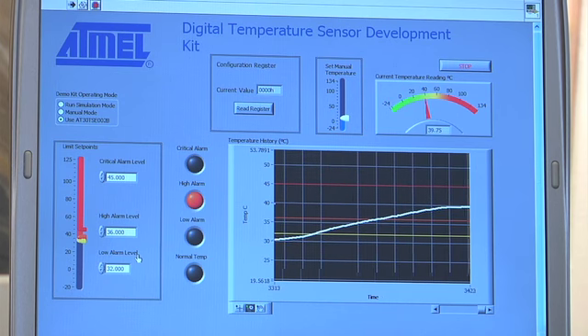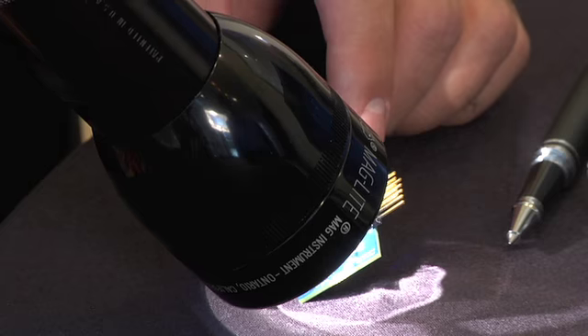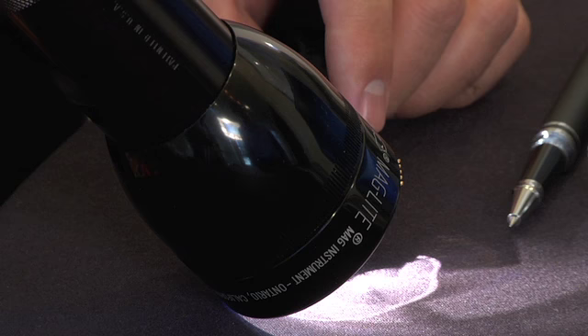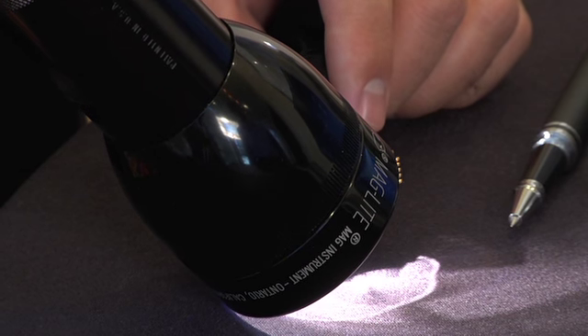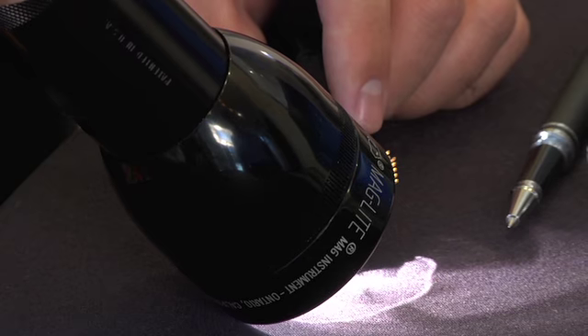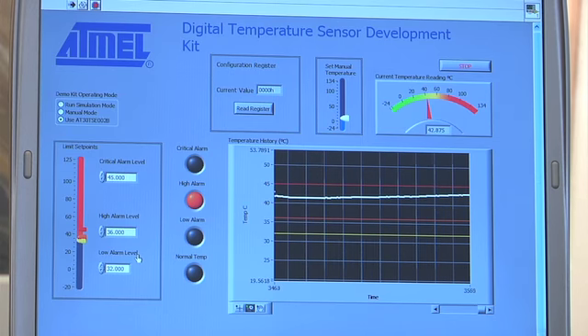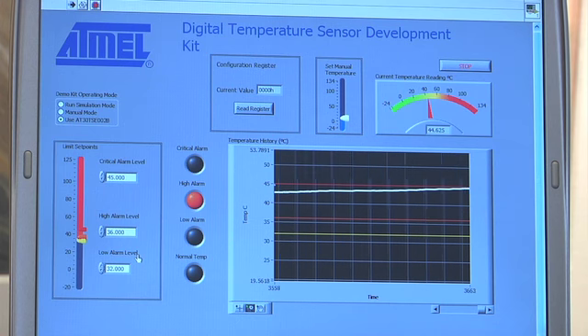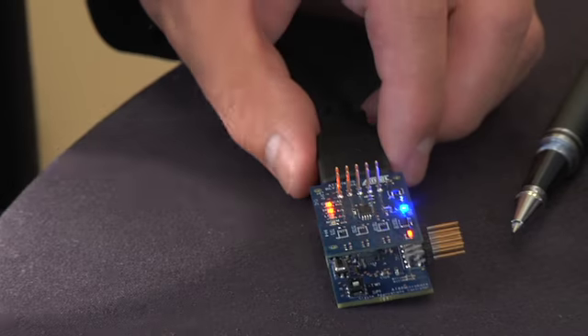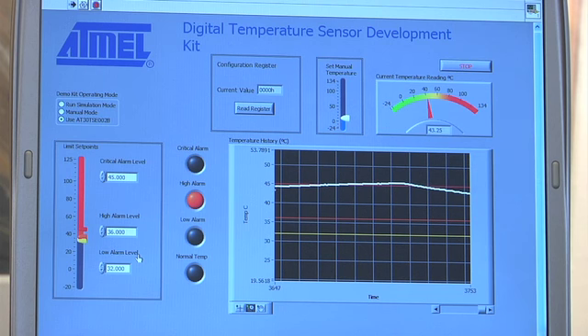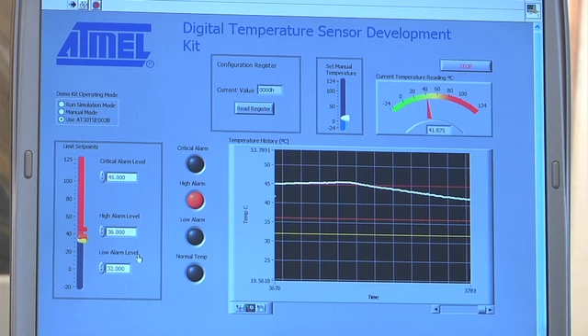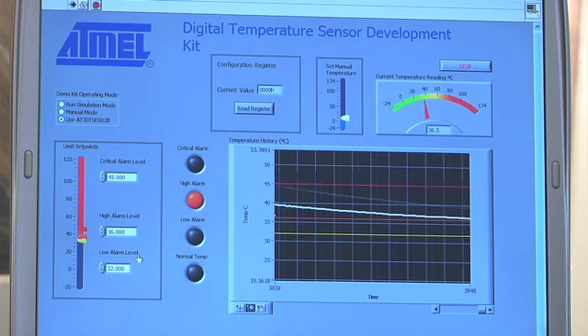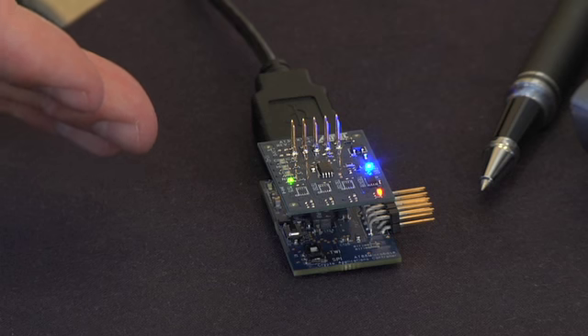And you can see the high alarm limit's already been exceeded. And if I take this heat source away, well actually I'll leave it on here and see if we can get the critical alarm limit to trip. And that critical alarm limit could be set to indicate the device has gotten extremely hot and you need to shut down the system altogether versus just turning on a cooling fan. And there we go. Bingo. So now it's tripped the critical alarm as well. And if I take away the heat source, you can see the temperature drops pretty quickly. And the critical alarm has turned off, and the high alarm will also turn off once it drops below that orange line.